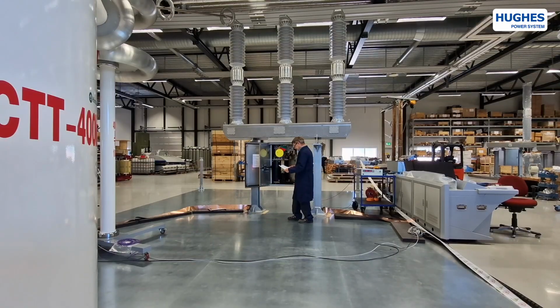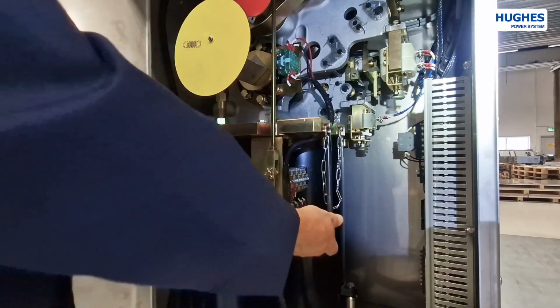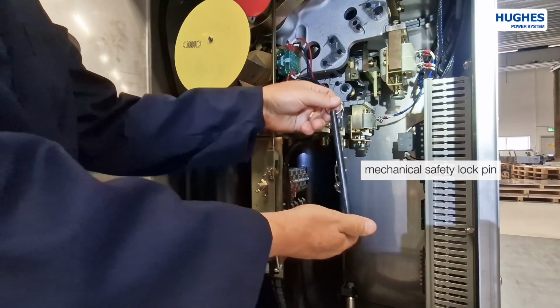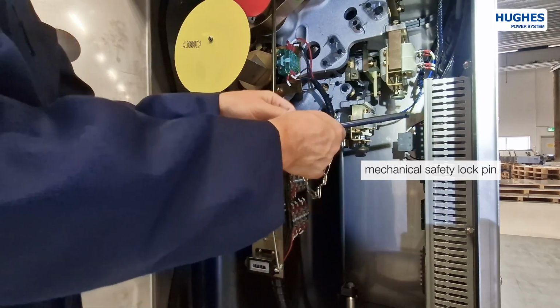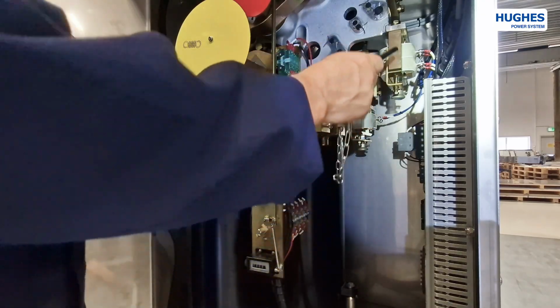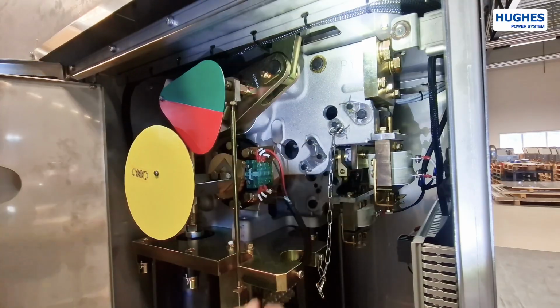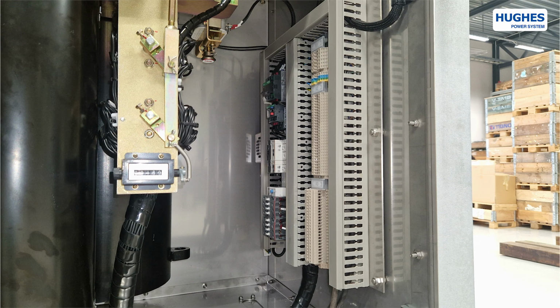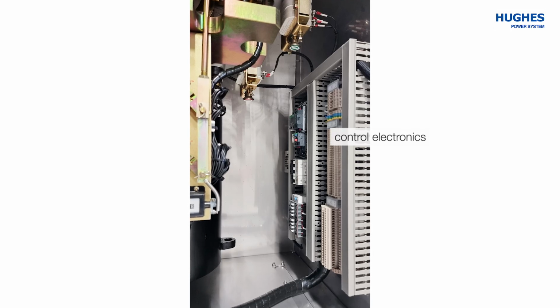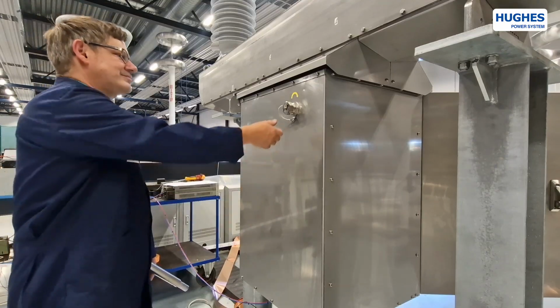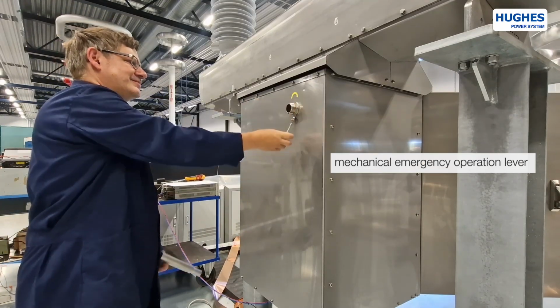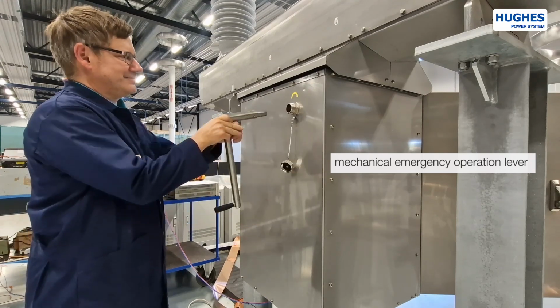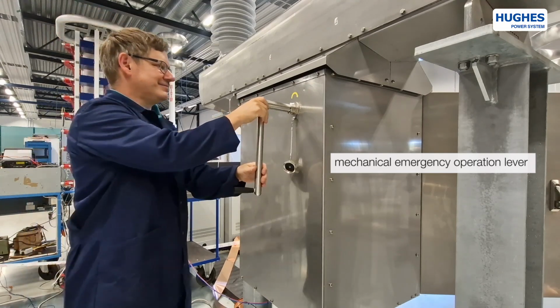A brief preview inside the cabinet. The mechanical safety lock pin is inserted into the trip and close mechanism. This creates a safe local blocking. Inside the spring operation mechanism are the mechanical operation counter and the control electronics with its automatic fuses. The mechanical emergency operation lever is adjustable to a comfortable operational length.